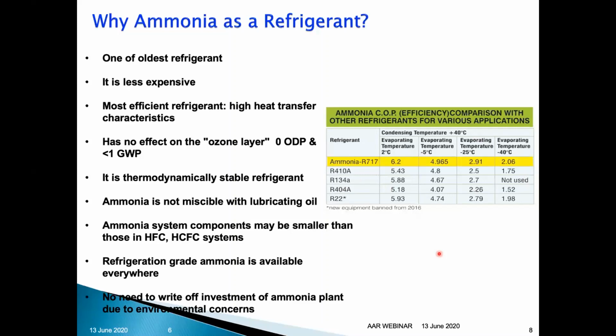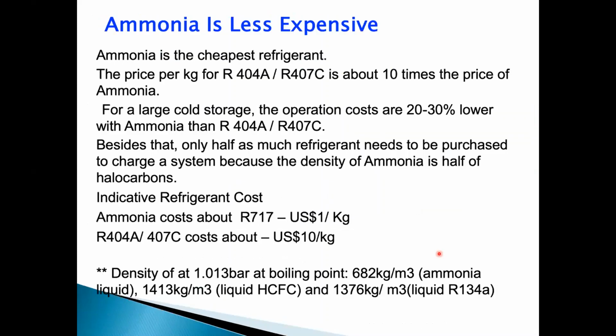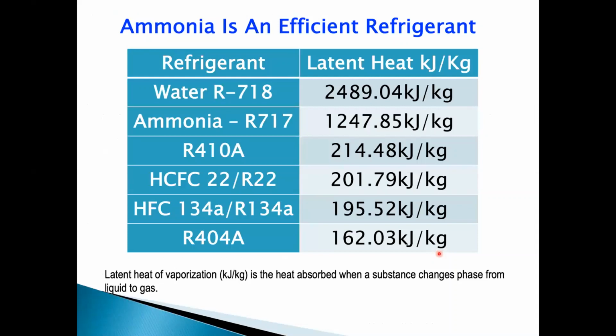The cheapest refrigerant, I told you, and I also told you its operating cost is much lower. How much lower, we'll see. This is what I was talking about, efficiency and why we need smaller equipment. Other than water, you have the highest latent heat for ammonia. Those who are in the refrigeration industry know the latent heat. It is the heat of vaporization that is absorbed when a substance changes phase from liquid to gas. So when we evaporate a refrigerant using heat from a product, that is the heat transferred from the product to the refrigerant. Ammonia has the highest heat capacity, that is 1247.85 kilojoules per kilogram. If you see all the others, they are almost a 1:5 ratio if you compare ammonia and other refrigerants. So that's why you need smaller components. You have a more efficient and more stable refrigeration system.